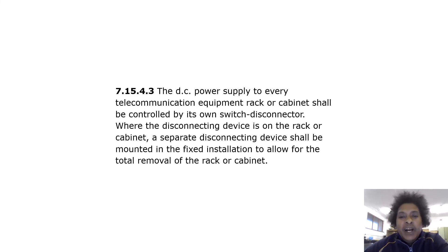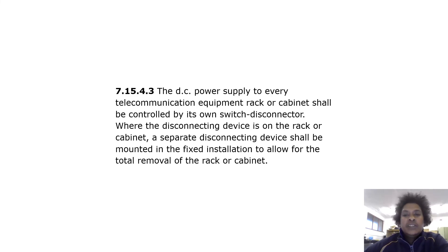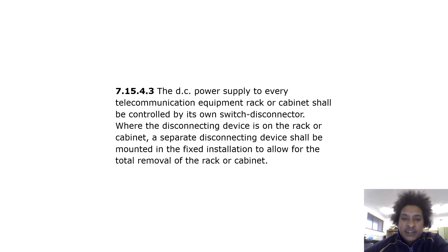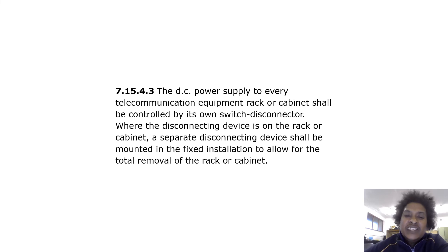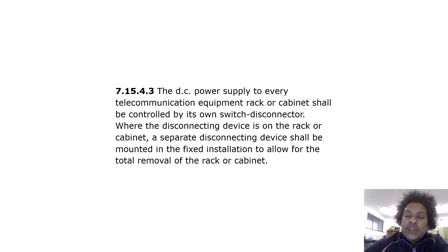The DC power supply to every telecommunication equipment rack or cabinet shall be controlled by its own switch or disconnector. Where the disconnecting device is on the rack or cabinet, a separate disconnecting device shall be mounted in the fixed installation to allow for the total removal of the rack or cabinet.